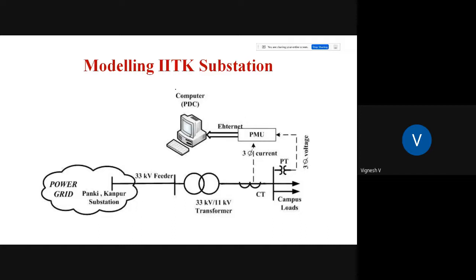We changed the taps of this transformer to produce very small changes in voltage, because if you have a major change in voltage, people would sense it and there could be false alarms. So we did this exercise very early in the morning, like 3 or 4 o'clock, so that people would not notice the change in voltage levels.